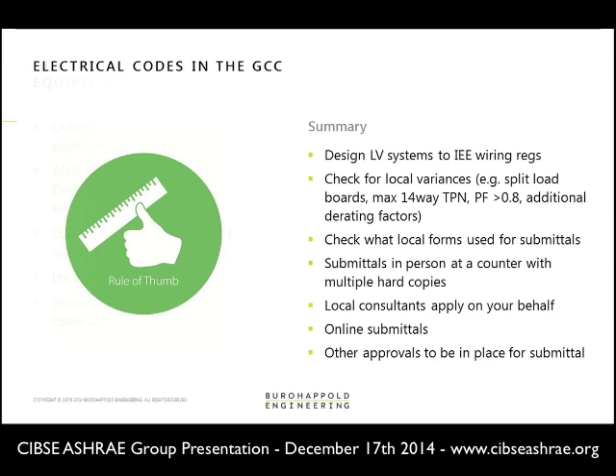So for example, in Abu Dhabi, split load boards are not permitted, and you're not allowed to use more than 14-way TPN boards. In Kuwait, you can't consider a power factor greater than 0.8 in your calculations, even if you have supplementary power factor correction equipment installed. Kuwait also requires additional derating factors that can significantly increase the size of your LV installation. So these are things that you need to be aware of when you're designing on top of the IEE regs.